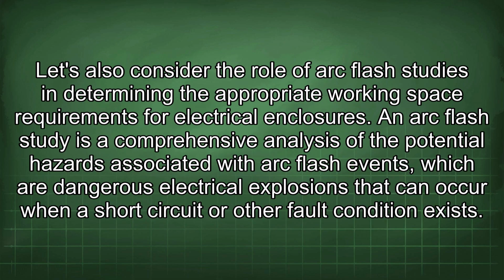Let's also consider the role of arc flash studies in determining the appropriate working space requirements for electrical enclosures. An arc flash study is a comprehensive analysis of the potential hazards associated with arc flash events, which are dangerous electrical explosions that can occur when a short circuit or other fault condition exists.